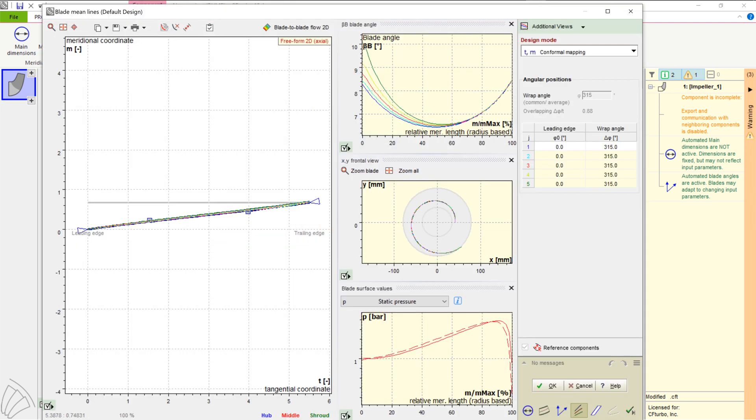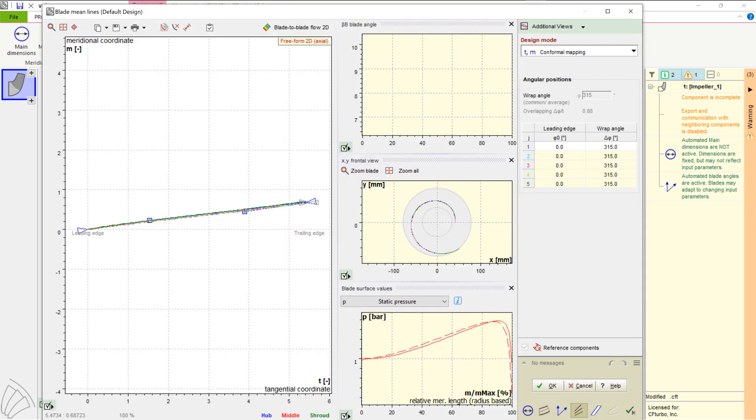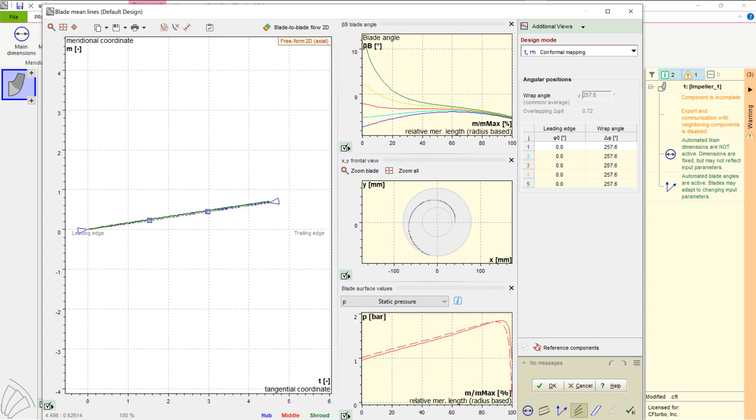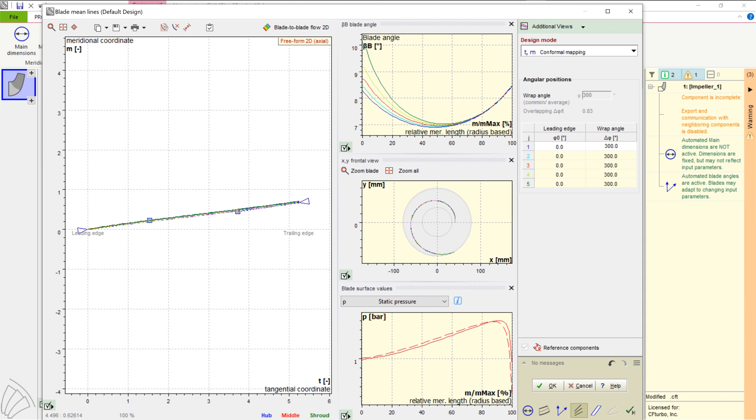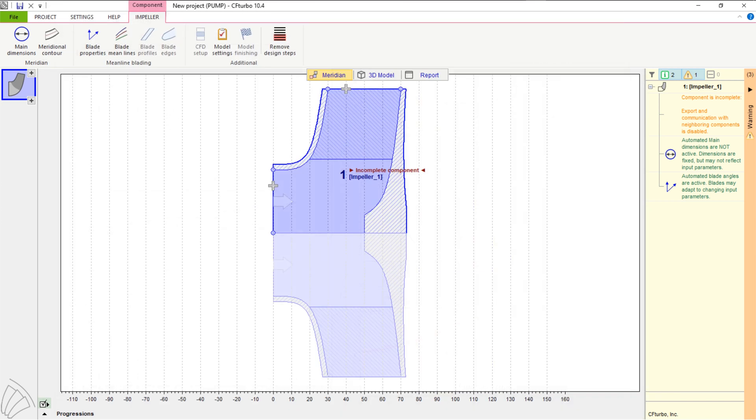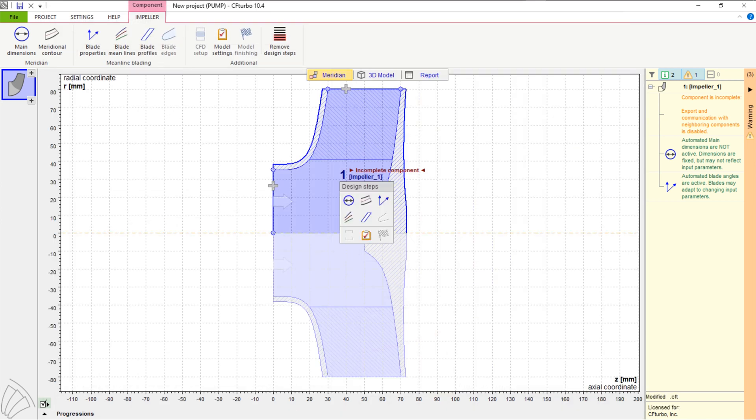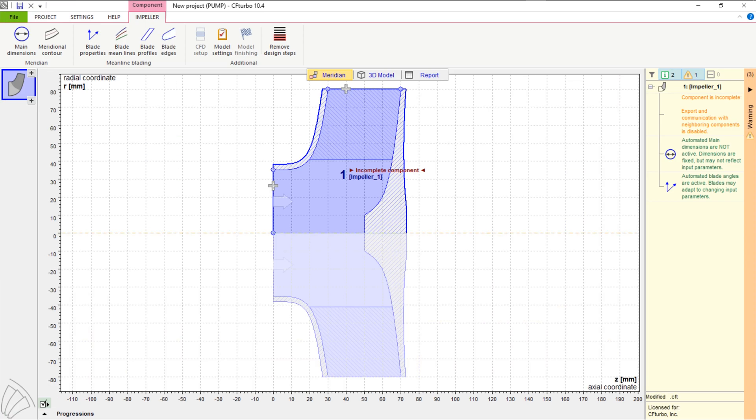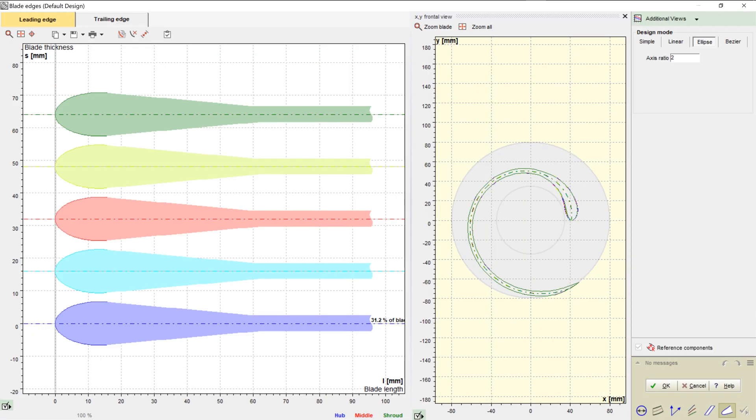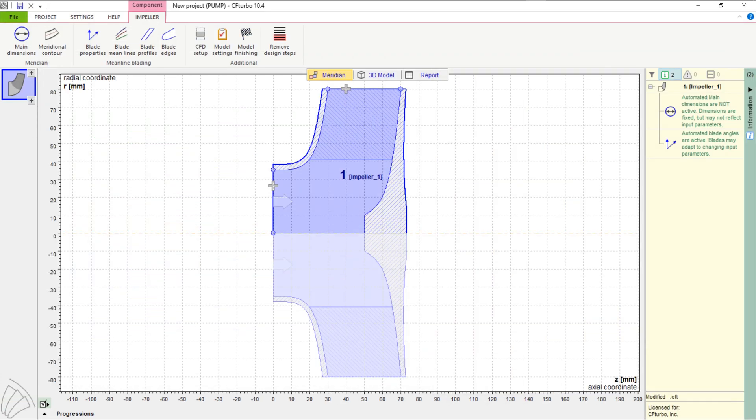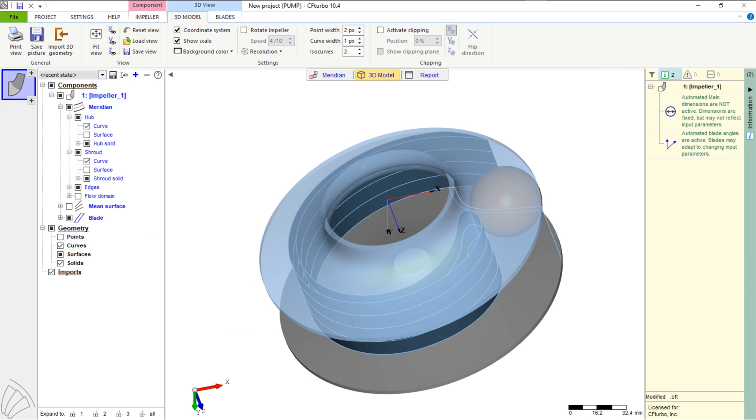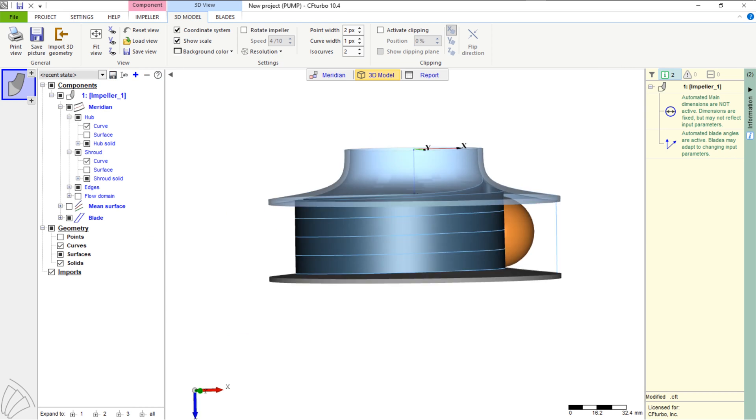The next design step is called meanline design. In this window, we determine the wrap angle of the blade and the blade curvature between leading and trailing edges, which has high impact on the performance of the impeller. There are different design modes available based on conformal mapping or by setting beta progression directly. Meanline design will be followed by blade profiling and afterwards defining the shape of leading and trailing edges. The last two steps are just briefly touched.